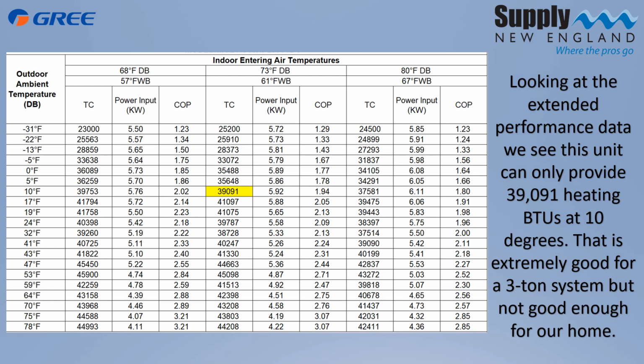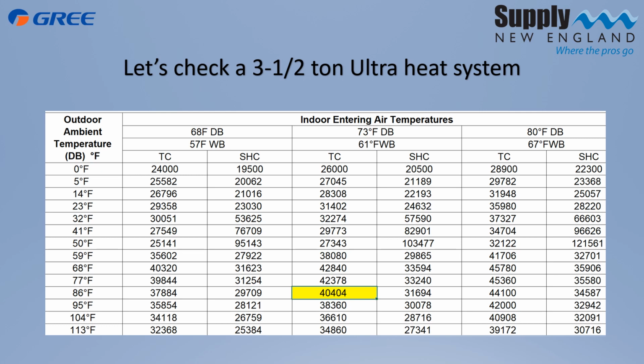So back to our extended data, but this time on our heating side. At 10 degrees, 73-degree indoor, because again, that's the closest I can get to our designs, this system provides us 39,091 heating BTUs. That's really good for a 3-ton system, but it's not good enough for our home. So it's not going to work. Let's take it up a notch. Let's look at that 3.5-ton ultra heat system now.